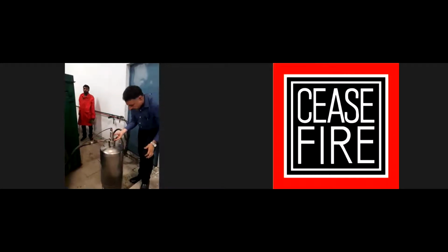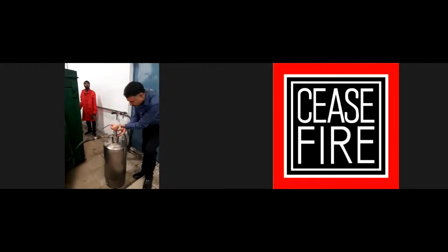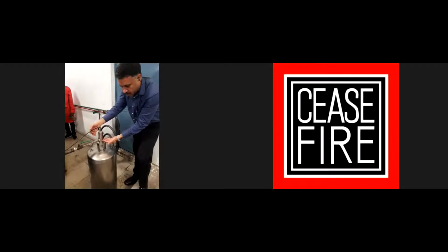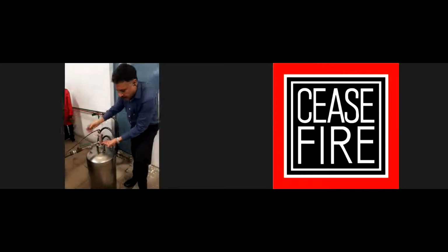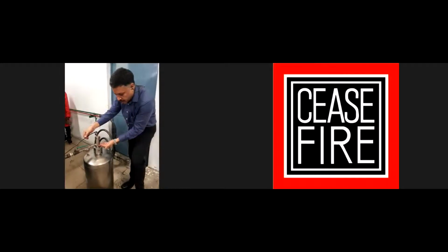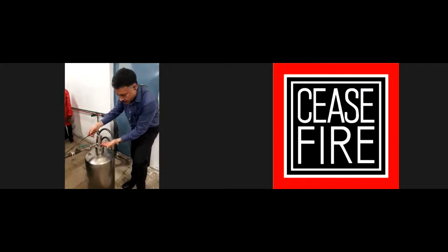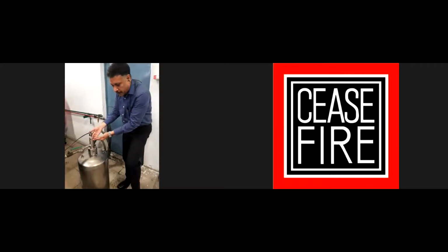It has got a piston here. So till now, because there is a pressure in the tube, the piston is closing the outlet of the water. The moment the tube is ruptured inside, the gas will be removed because this tube is pressurized till now. And once the gas is removed, this piston will come upside, and the flow of the water will start from here, and it will go inside to the nozzles, and it will suppress the fire.